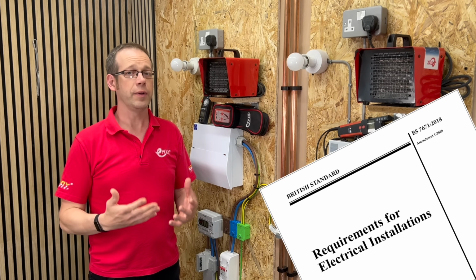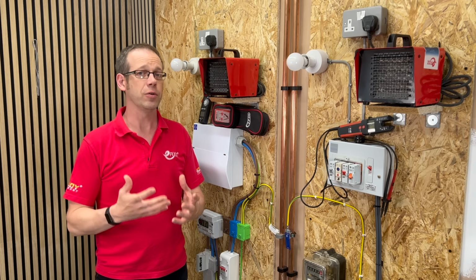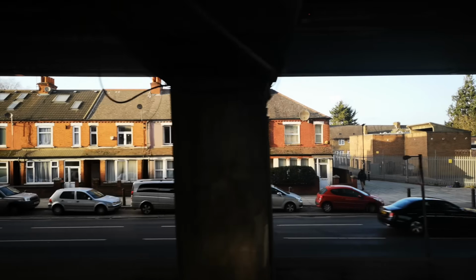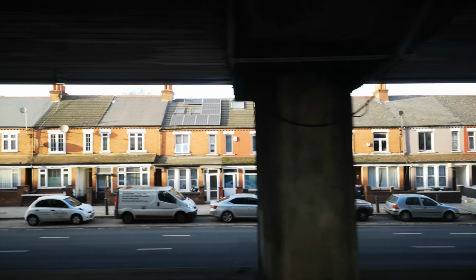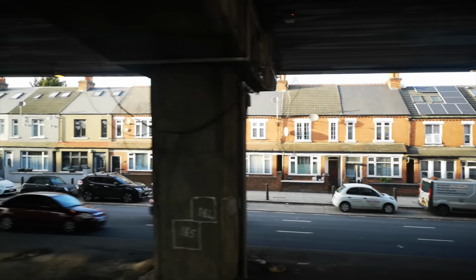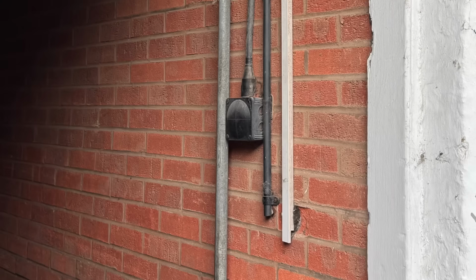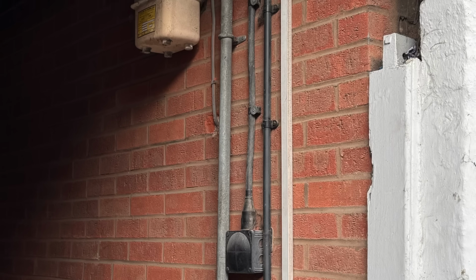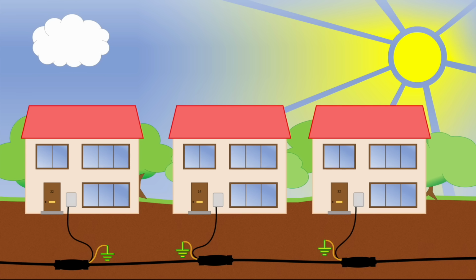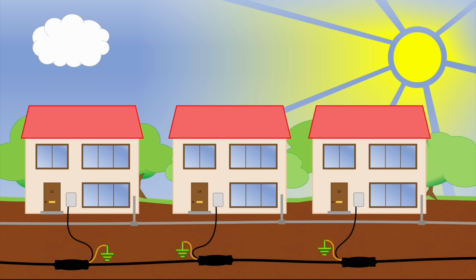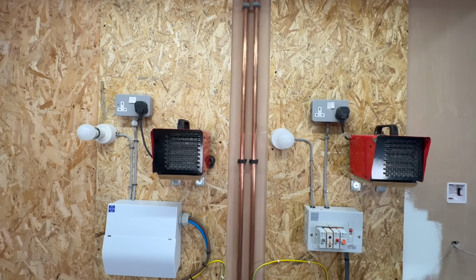But even with that hole in the regs plugged, a PEN fault can still cause other serious problems, because in older properties where most of the aged supply connections are failing, there's very often a metallic pipe coming into the property carrying water, and maybe another bringing in gas. Much like the supply cable running down the street, these pipes connect to a main pipe to supply the property with the resource that it carries. For simplicity in this video, we're just going to show the water pipe, not the gas pipe, although all the same principles apply. We're going to consider 2 different scenarios.